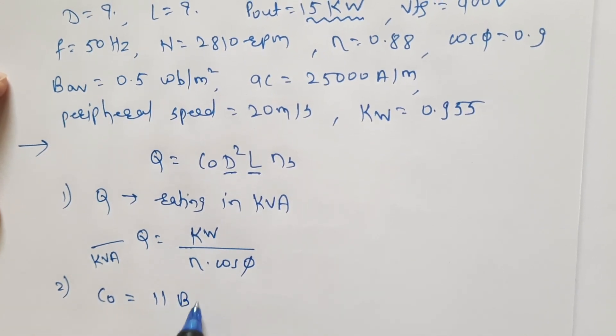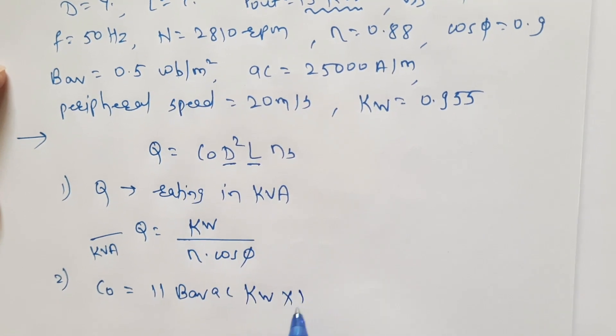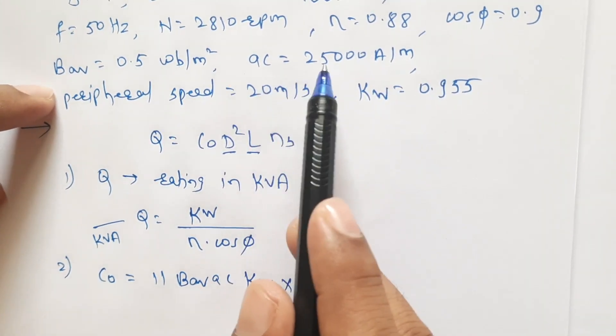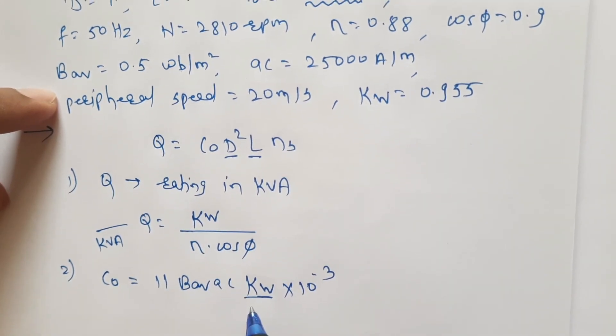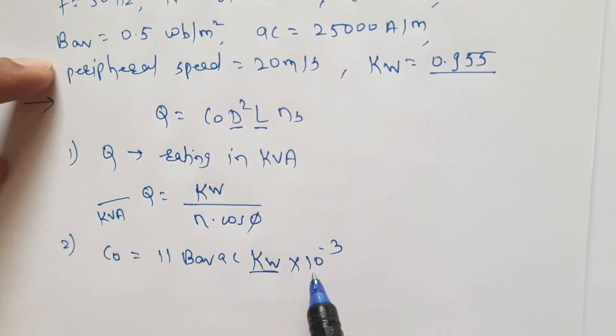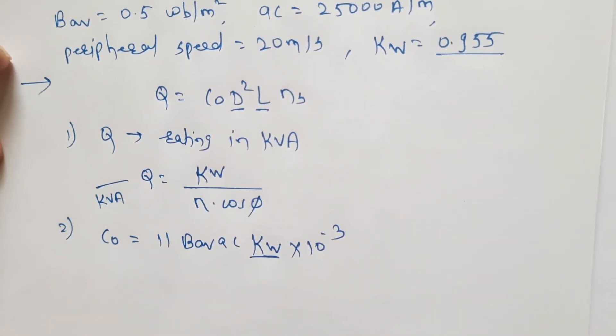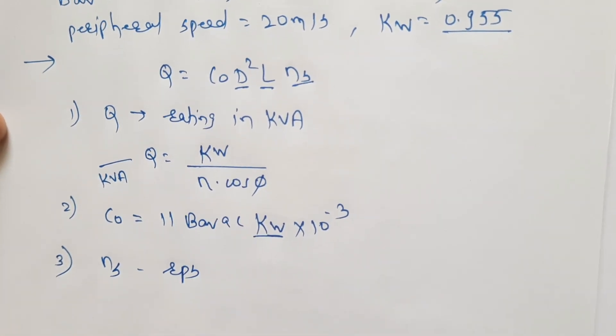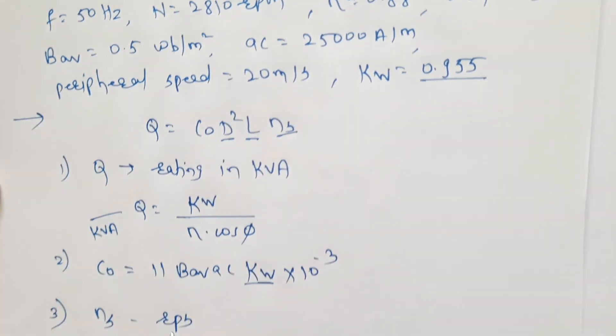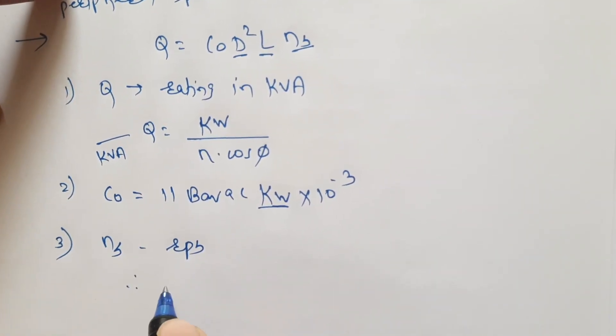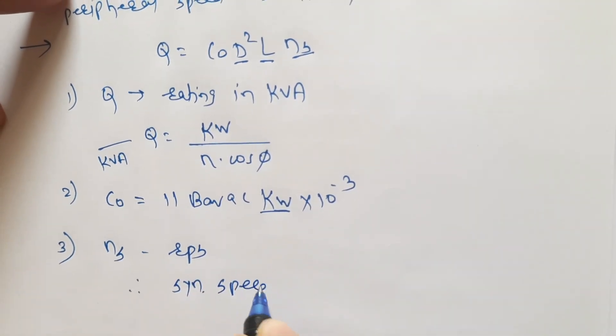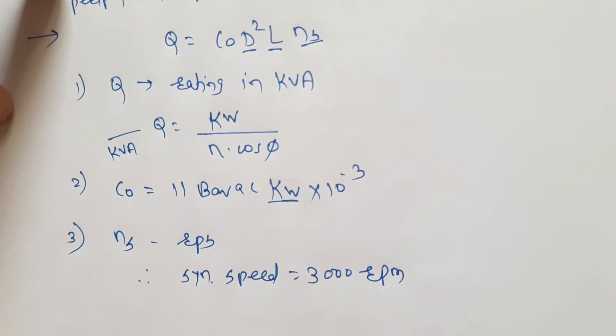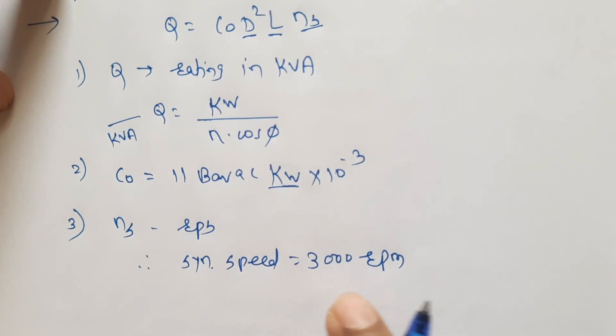So first we convert to input KVA using Q equals KW divided by efficiency into cos phi. The second step is to find the output coefficient C0, which equals 11 times B_AV times AC times Kw into 10 to the power minus 3. The third step is to find small ns, the synchronous speed in RPS. The actual speed given is 2810 RPM, so we assume the nearest synchronous speed is 3000 RPM, since N is always less than Ns.